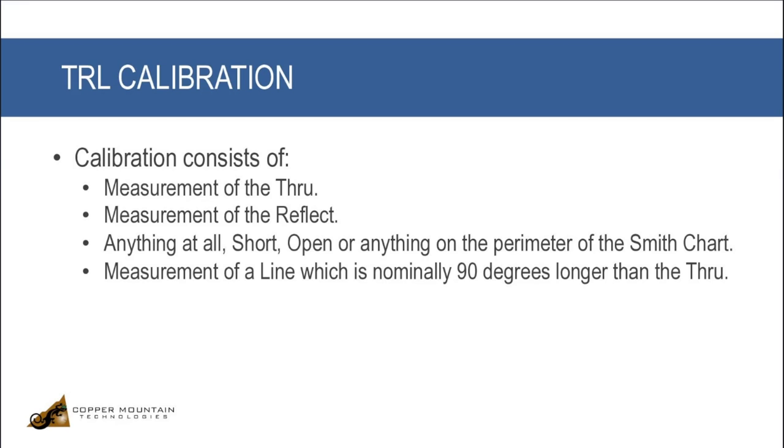the gentleman who was talking about just using this with the cable open. Anything at all can be used. A short, an open, anything on the perimeter of the Smith chart can be used for the reflect. That means, yes, you can just leave this open. The only caveat there is that whatever you do on port one has to be done on port two. So if these two things look the same as an open, you can use this as your reflect.